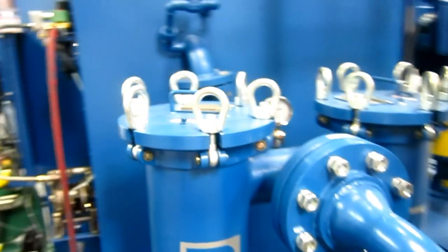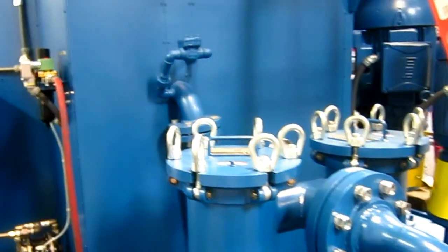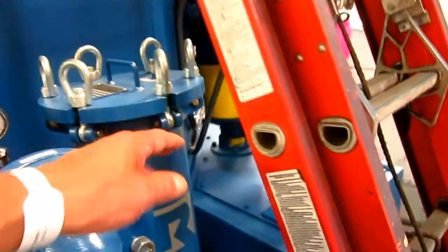You pop those off, pull the basket out, and change the micron bag. Micron bags are available anywhere from about 10 to 20 microns up to 800 or more. Water comes directly out of the pump, goes into the inlet of the filters, through the filters, out of the filter, through an air break, and to the manifold system.